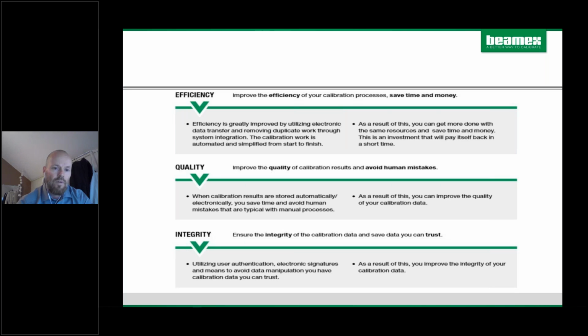So if you have a digitalized solution in place, you cannot go and edit or manipulate the data in any way. It's secure from the moment you hook up the instrument to the calibrator, to when it's uploaded into the database and backed up. During that whole process it cannot be manipulated, and you can really trust the data. So data integrity is really a key here.